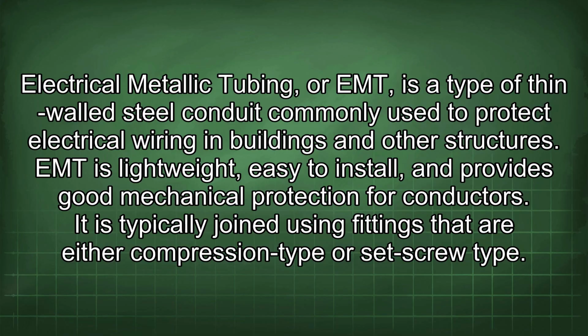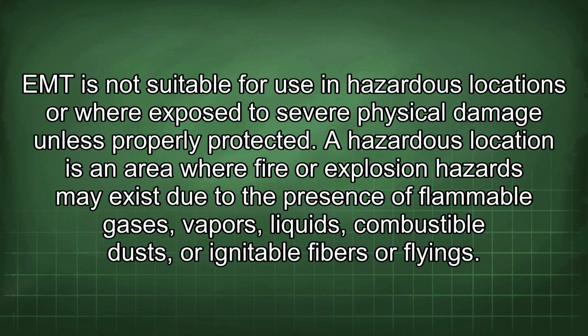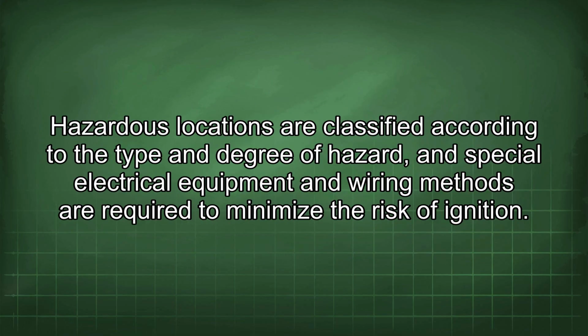It is typically joined using fittings that are either compression type or set screw type. EMT is not suitable for use in hazardous locations or where exposed to severe physical damage unless properly protected. A hazardous location is an area where fire or explosion hazards may exist due to the presence of flammable gases, vapors, liquids, combustible dusts, or ignitable fibers or flyings. Hazardous locations are classified according to the type and degree of hazard, and special electrical equipment and wiring methods are required to minimize the risk of ignition.